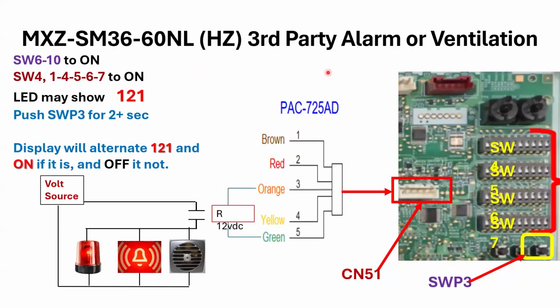This is a pretty cool option here. So from the outdoor unit, we've always had this CN51 connector. And what we can do is get an output out of the board of the outdoor unit. You get this 5-pin harness. Here's the part number for it. And you take wires orange and green, in this case 3 and 5. And what this does is it outputs 12-volt DC power out of the connector on these wires.